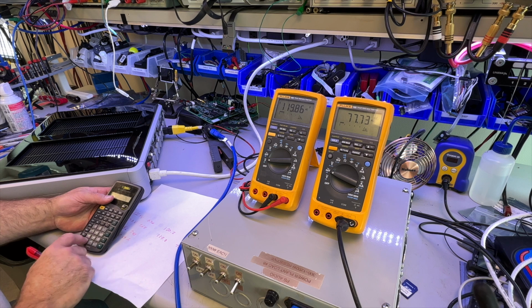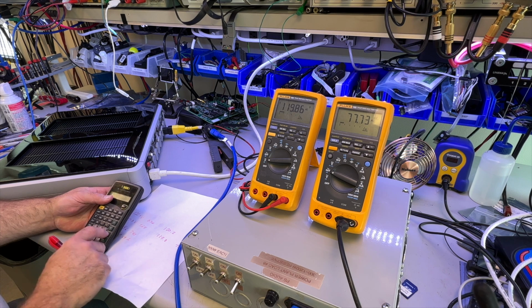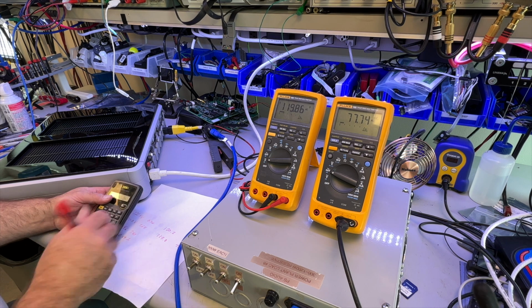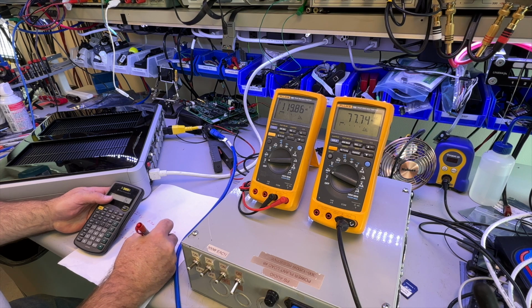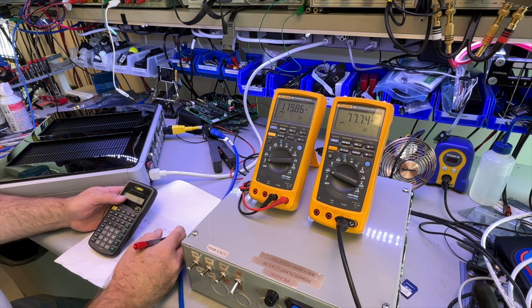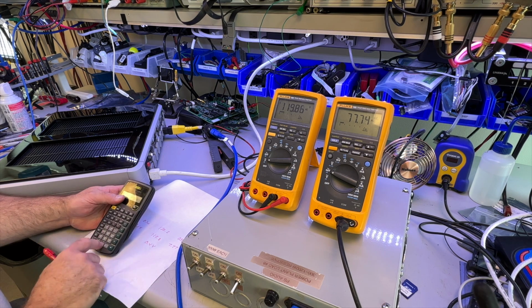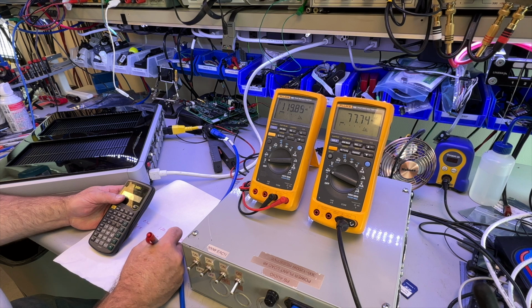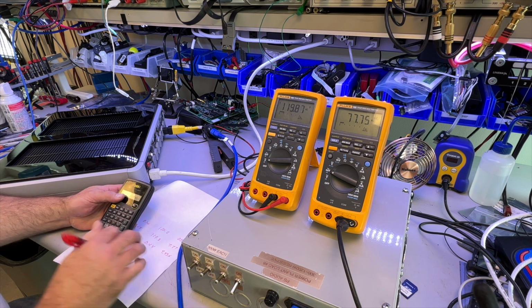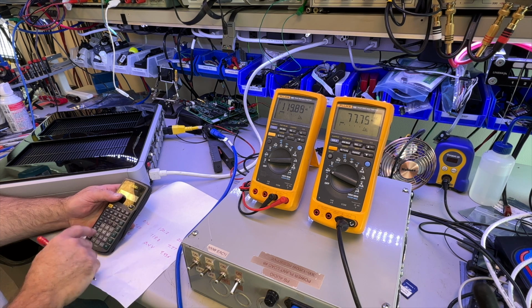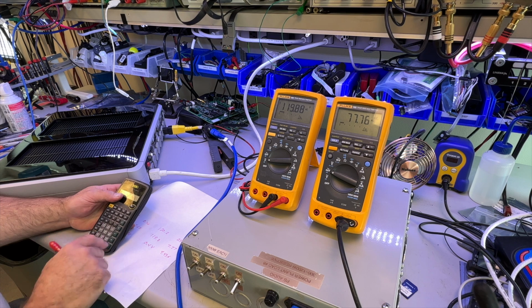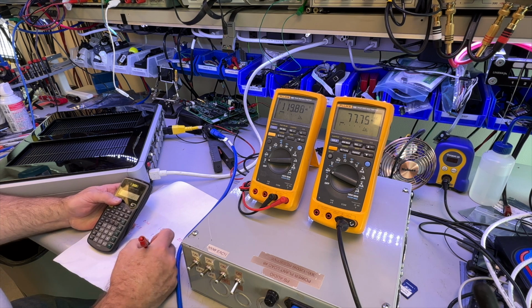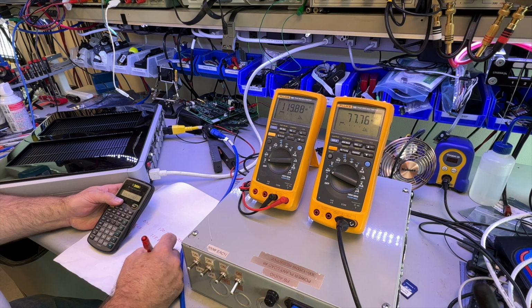So I'm going to do the same math. I'll take 120.2 and subtract 119.8, that gives me 0.4 volts, so 400 millivolts. And the current is now 7.77 amps minus 0.34 amps, which is 7.43 amps. If I take 0.4 divided by 7.43, I get 0.054 ohms.